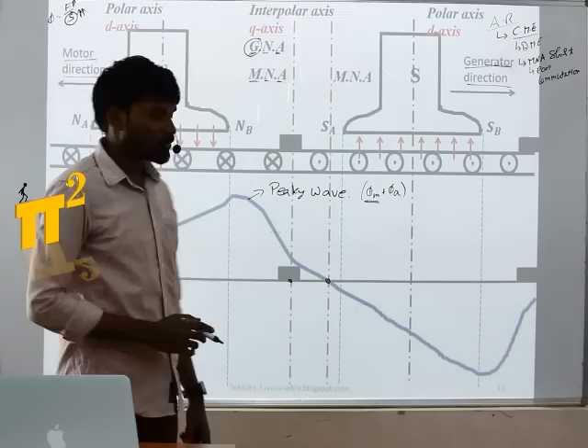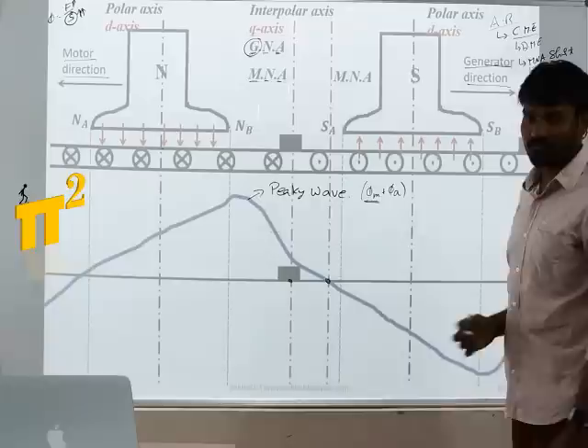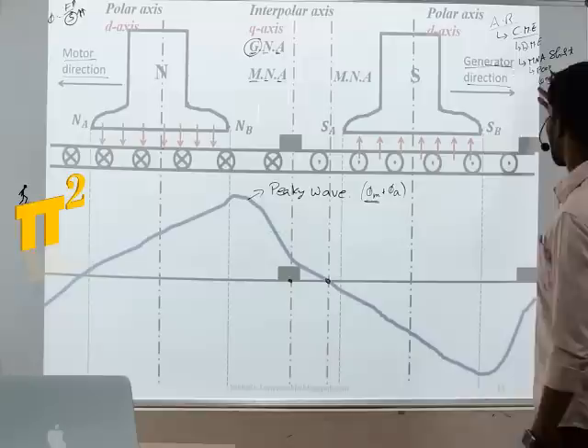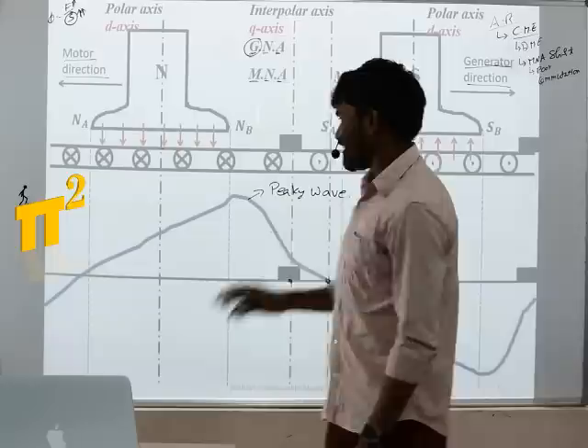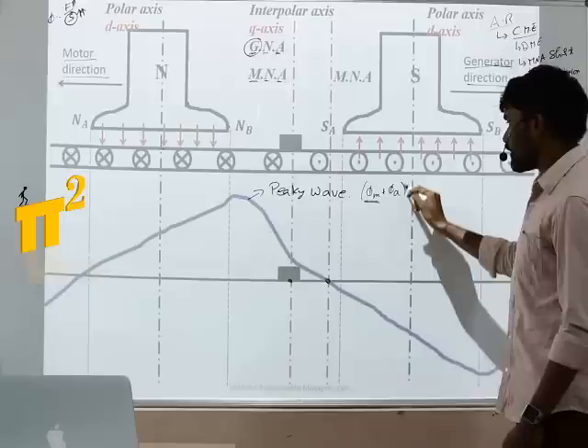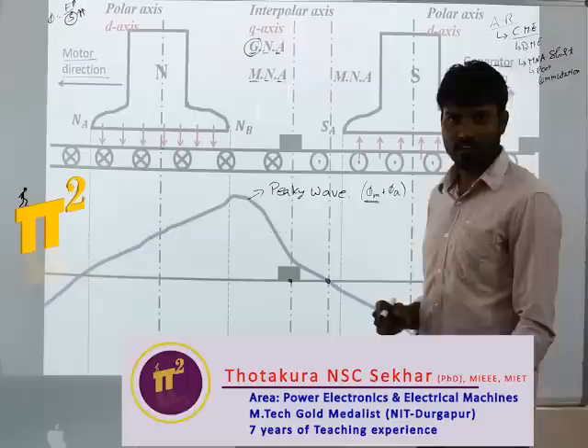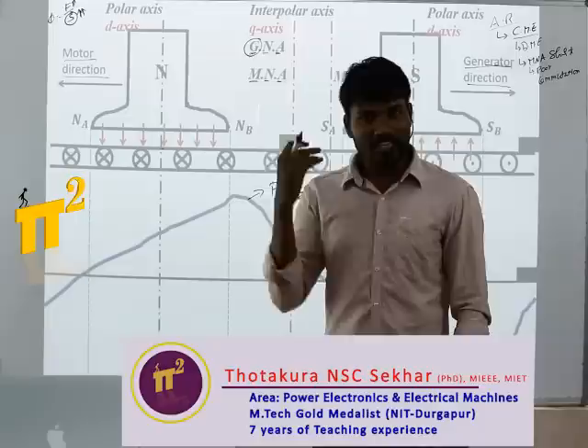Poor commutation means sparking at the brushes, which leads to more maintenance and damage of commutator segments and brushes. One way to avoid this is to allow no current in the armature conductor — if IA is zero, there is no armature reaction, no MNA shift, and no sparking. Good commutation results. But if no current flows in the conductor, there is no use of having a machine.